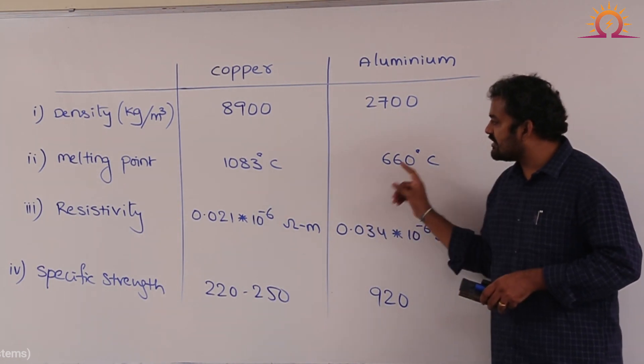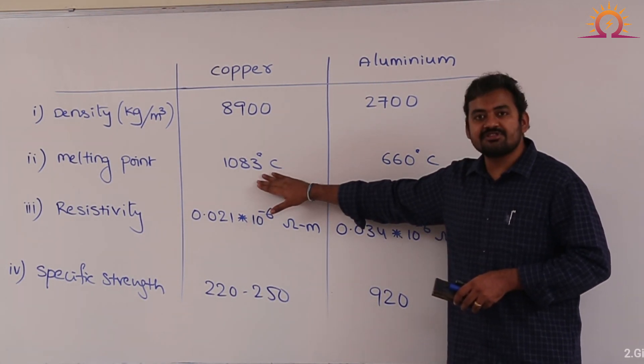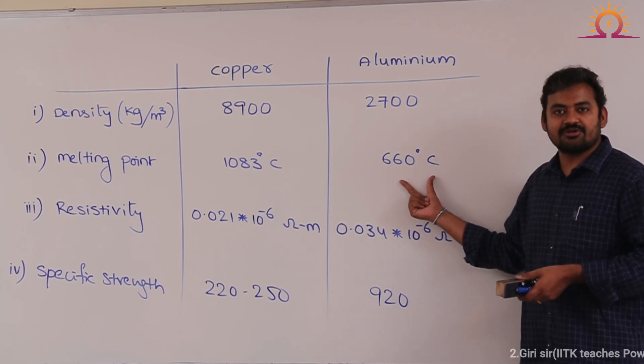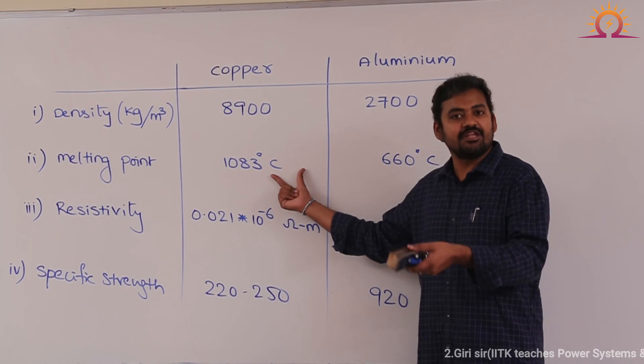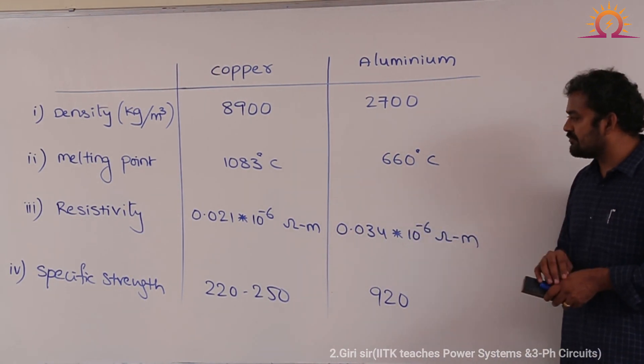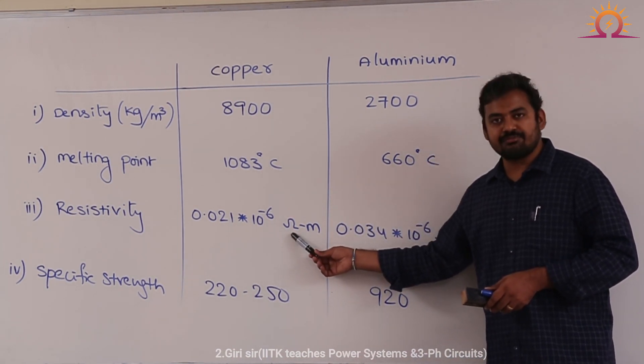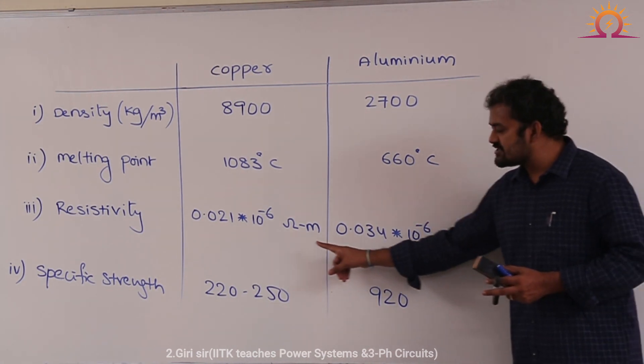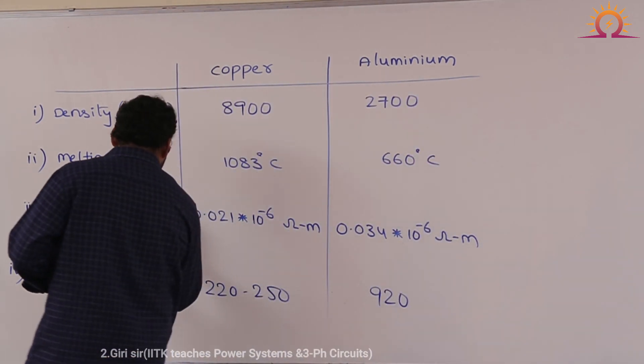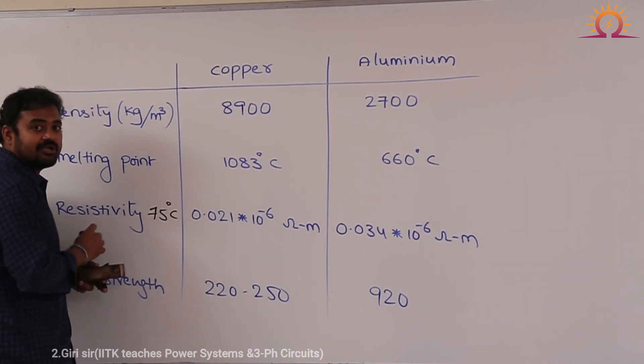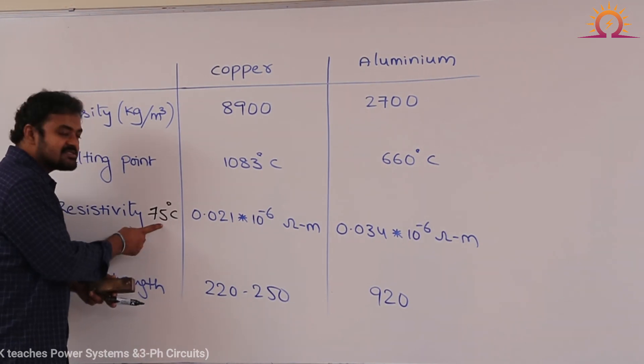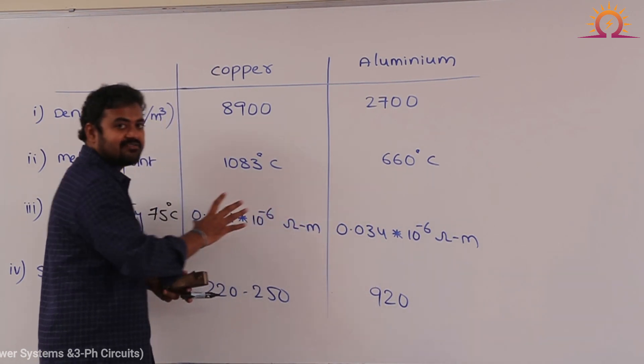However, if you look at the melting point, copper has a higher temperature withstanding capacity — 1083 degrees centigrade — whereas aluminum's melting point is 660 degrees centigrade only. Therefore, copper can withstand higher temperatures, which is a superior quality. Coming to the resistivity point of view, copper resistivity is 0.021 × 10⁻⁶ ohm-meters. These resistivity values are valid at a temperature of 75 degrees centigrade, not at room temperature, because when a machine is under full load condition, the average temperature inside the machine will usually be 75 degrees centigrade.